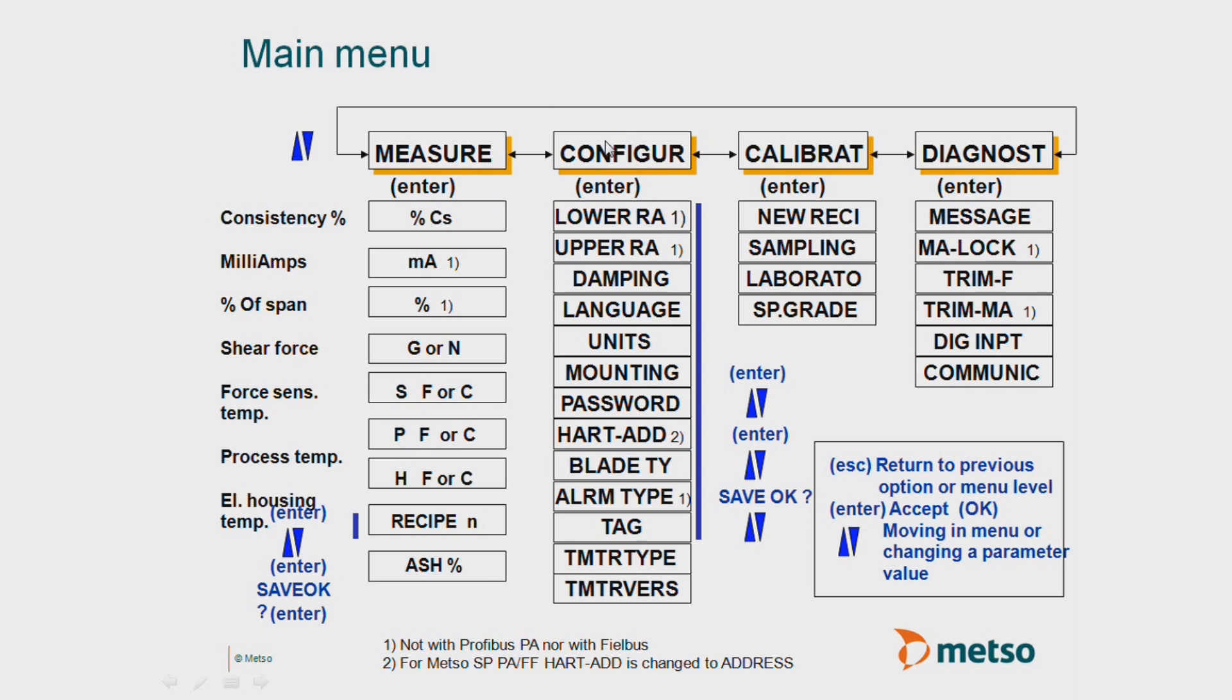Now when we're calibrating configuration and calibration of a SmartPulp, we're going to focus on these two menus. When we go into configuration, what's the lower range? In our case, the lower range is 2% consistency. That's going to match the 4 milliamps. Then we go down to the upper range here, which is going to be 5% consistency in our scenario, and it's going to match 20 milliamps. Then we can skip down to our units. In our case, we're just going to keep it at grams, and temperature is going to be F for Fahrenheit.